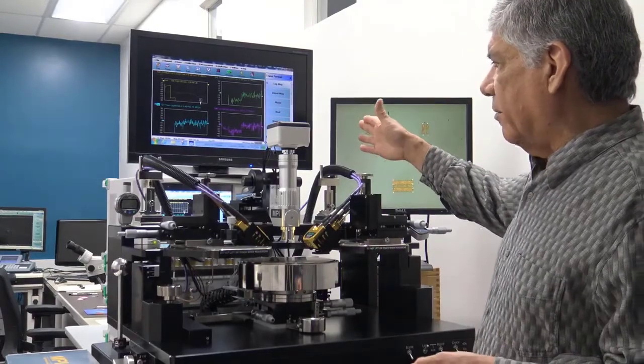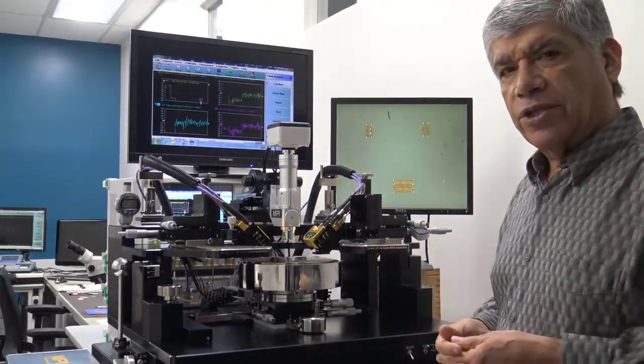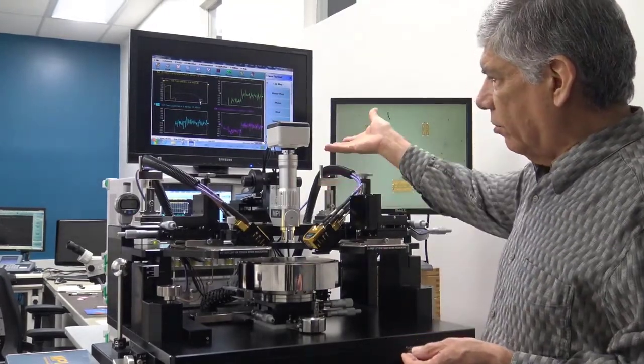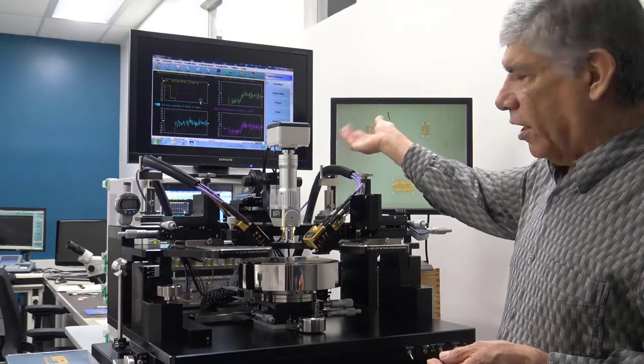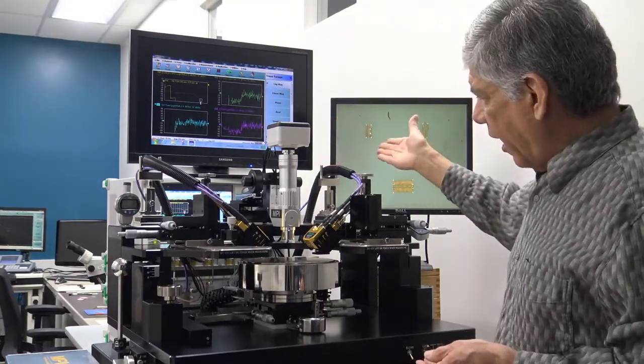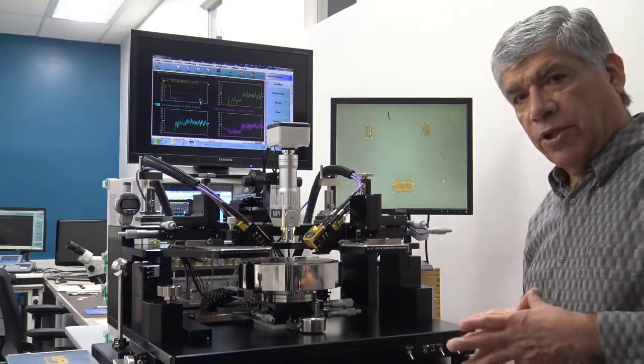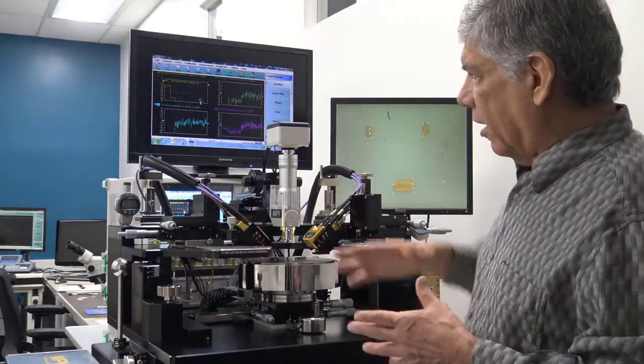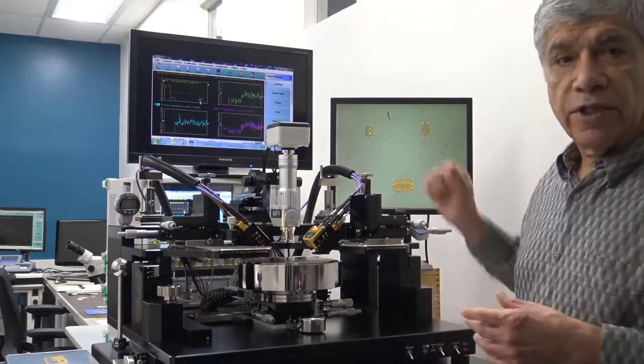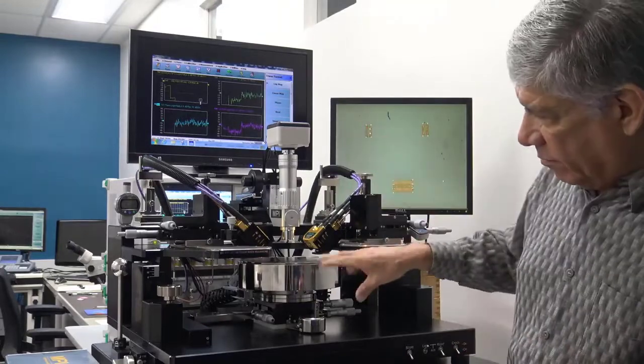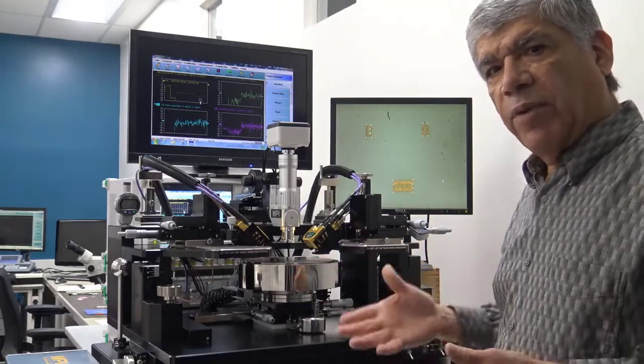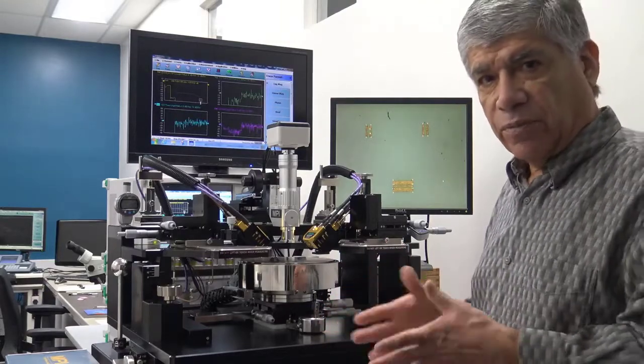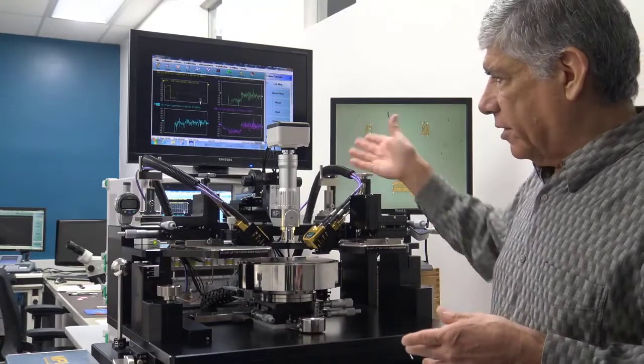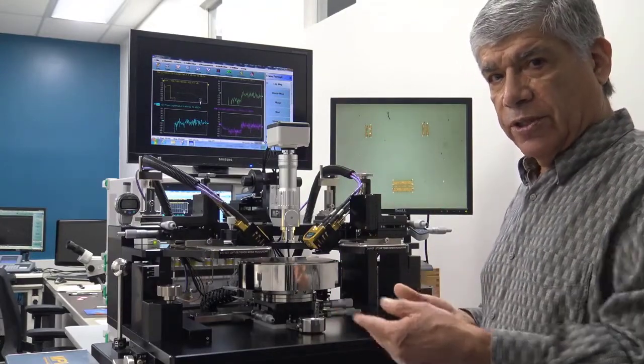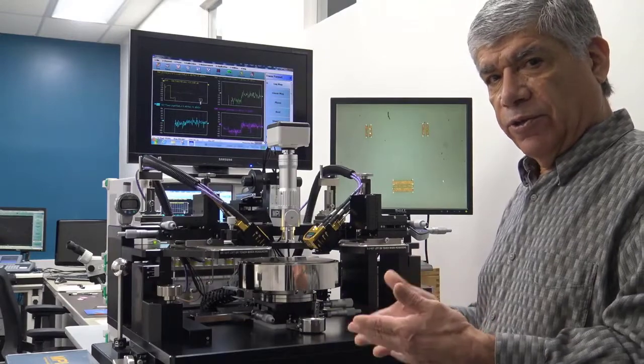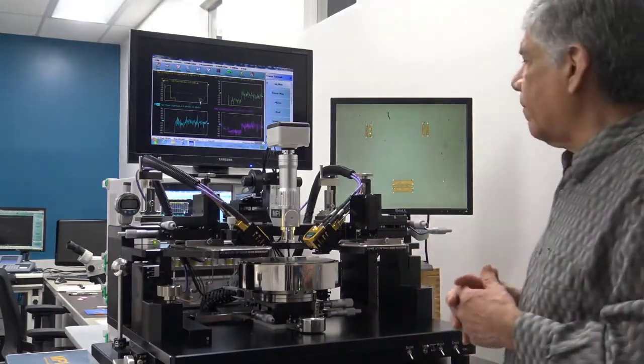So the system is typically going to be set up behind the probe station, and normally you would want to elevate the test port of the VNA so that the cables have good access to where the modules are going to be mounted. And so the elevation of the system is your first consideration. In this case, we had a system mounted on one of our synthesizers, which can often be used as a second source for things like mixer measurements or differential measurements. This particular system has two internal sources, and we can do active differential tuning just using the internal sources.